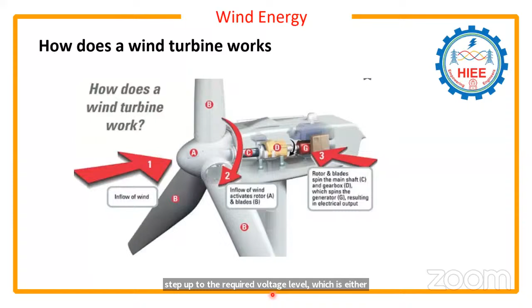Next slide please. Just to add, this is the place where you get 690 volts AC output - the output of the generator is electrical energy at 690 volts through cable. That cable comes from top to bottom and connects to the transformers to step up to the required voltage level, either 11 kV or 33 kV. Generally the industry norm is 33 kV - we always step up at 33 kV to reduce line loss.